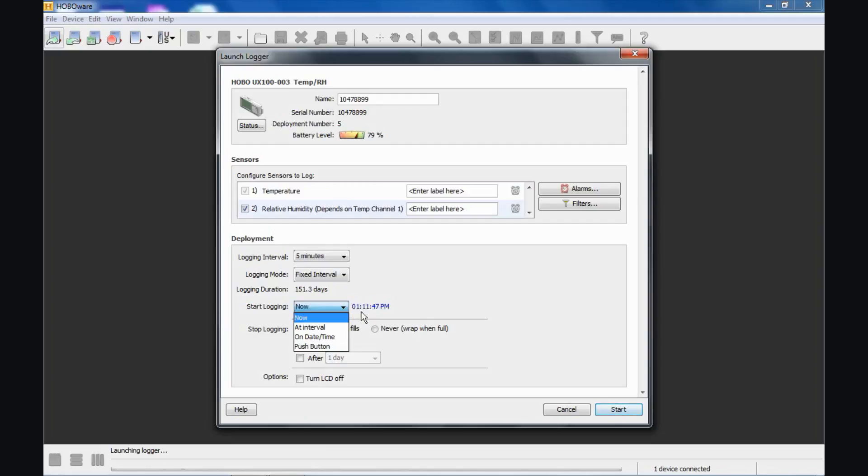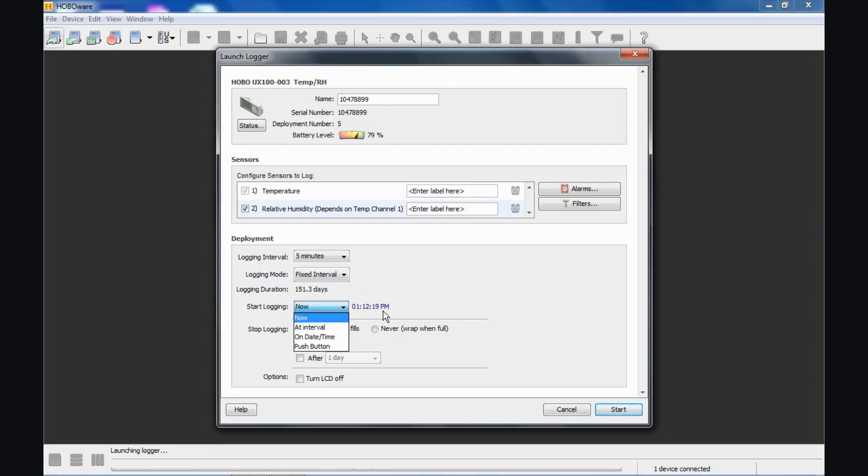Notice to the right, we see a clock that is counting seconds and minutes and hours. This is from our computer clock. The logger, or HoboWare I should say, uses this time and date as its start time and date and records it in the data file as a fixed value when we launch the logger. That's important to note because if your computer clock is wrong in your computer or in your launching device, because we do have devices called data shuttles which will be covered in subsequent videos—if the clock in the shuttle or the computer is incorrect, then your time and date in your data file will be incorrect. This is only when launching the logger. When you read out, you can read out data loggers with a computer with a different clock and it doesn't matter. It just matters about the computer that's launching it because that's where that start time and date comes from.